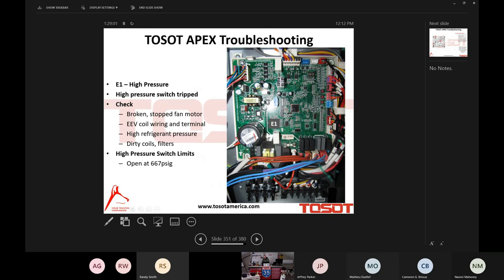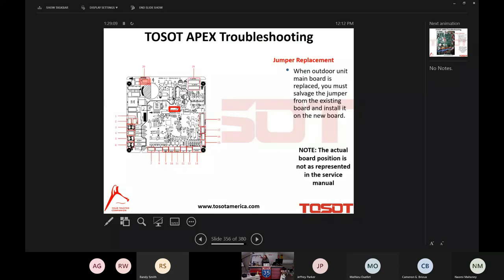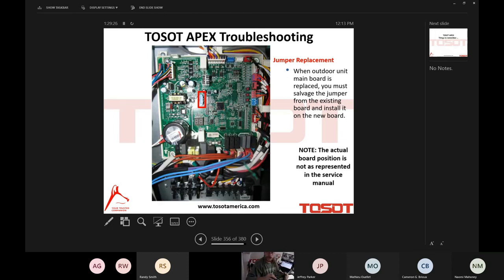And again, that is where that E1 would be displayed on the outdoor board, the LED screen of the outdoor board. If the outdoor board is ever replaced, highly unlikely, but just telling you it could happen, there is one item which must be salvaged from the old board and moved to the new board, and that is a jumper. That is where the jumper would go. You can see this is a brand new replacement board. So there's a receptacle for the jumper, but there's no jumper. You would have to salvage the jumper from the existing board and bring it to the new board.